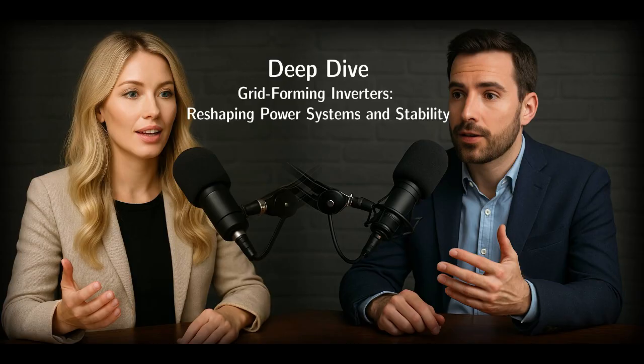And what's crucial to grasp there, Alex, beyond the obvious issues like frozen equipment, was the really severe loss of grid inertia. That's the system's natural cushion, right? The kinetic energy stored in all those big spinning traditional generators. The shock absorbers, basically. Exactly. As those tripped offline, the grid lost that inherent stability, that ability to ride through disturbances.